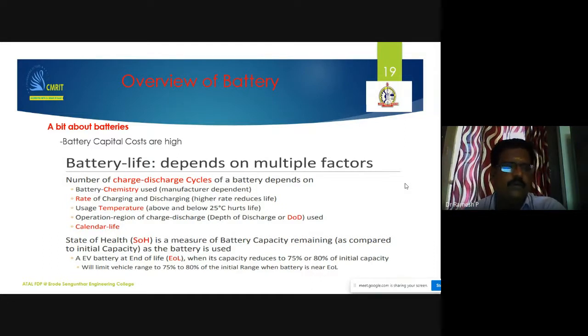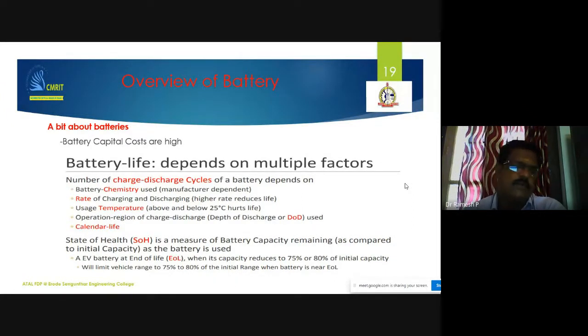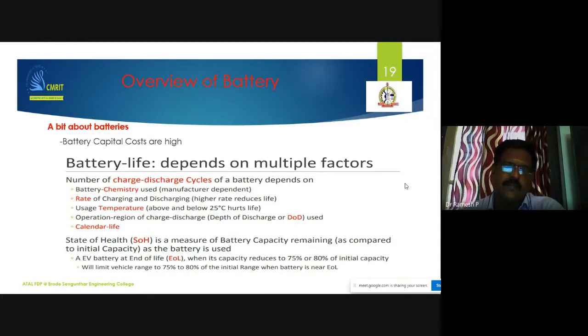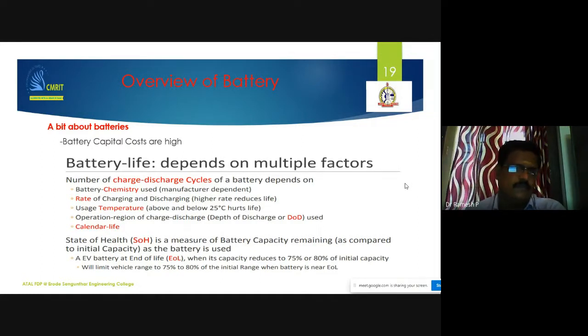Also consider calendar life. For example, once the battery is 1 year old, the capacity definitely decreases by about 1 to 2% of the overall rating. As calendar life increases, there will definitely be a reduction in battery capacity by a certain percentage, for example around 1 to 2% per year.